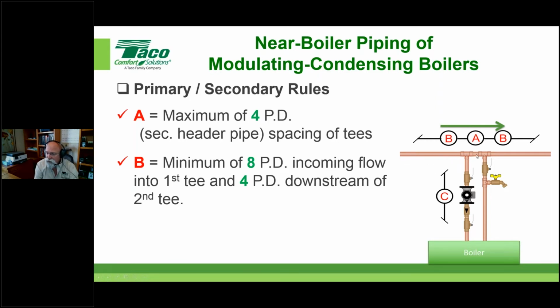Okay, remember, as close as possible here, but downstream, since we've already done the job that we were meant to do by getting this water mellowed out, and I'll show you what I mean by that in a minute, then once we've done that, we only need about 4 pipe diameters on this second side as a minimum. Again, conceptually, 2 T's in the middle of a nice long piece of pipe, okay? Understand that concept, you'll stay out of trouble.